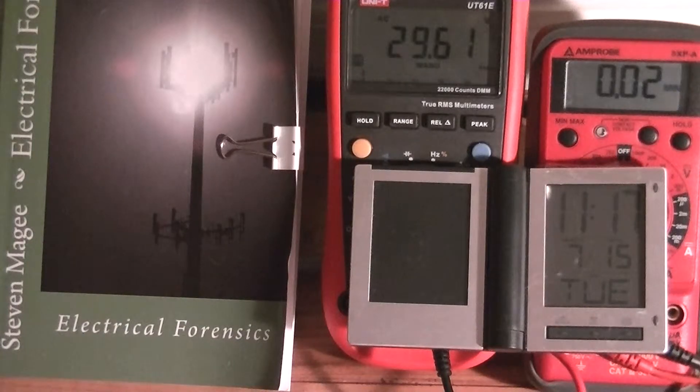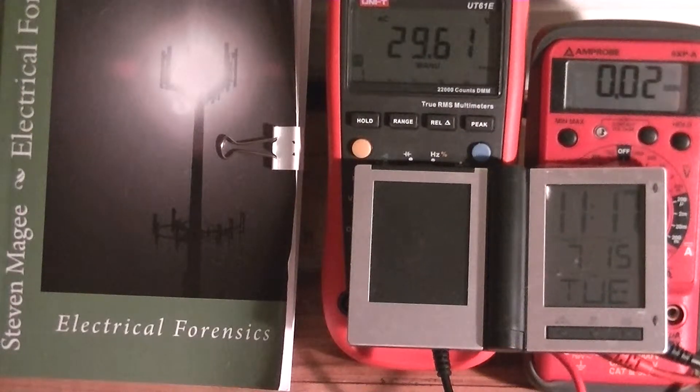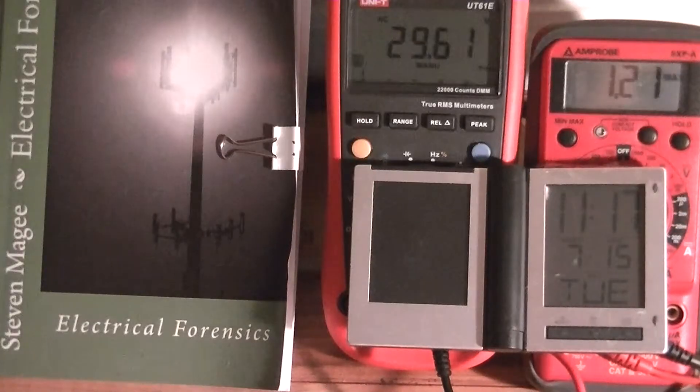Hi, I'm Stephen Magee and I'm the author of Electrical Forensics. We're going to look at electrical grounding systems using these two meters. On the right we have an Amprobe 35XP-A and it's recording the minimum and maximum values. The minimum value we got over the last couple of days was 0.02 and the maximum was 1.21 RMS.